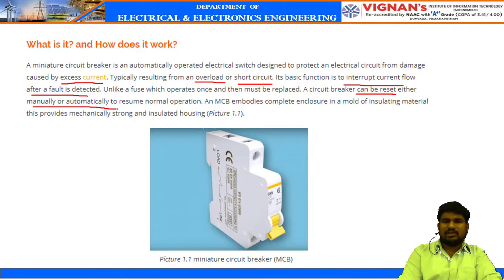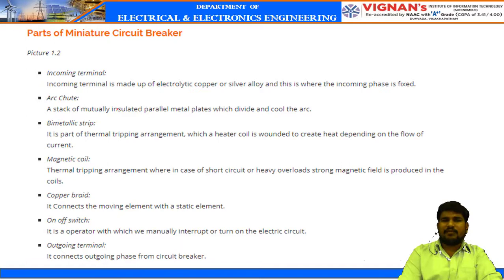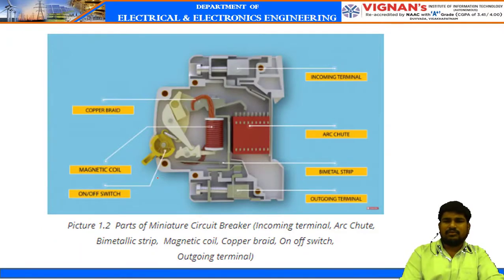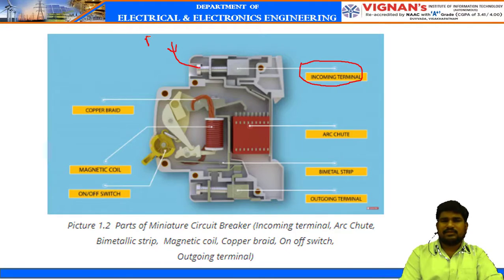Now let us discuss the parts of an MCB, that is, the construction of a miniature circuit breaker. In an MCB we have an incoming terminal, arc chute, bimetallic strip, magnetic coil, copper braid, on-off switch and outgoing terminal. The top one is the incoming terminal. For example, this is the supply, which is phase.